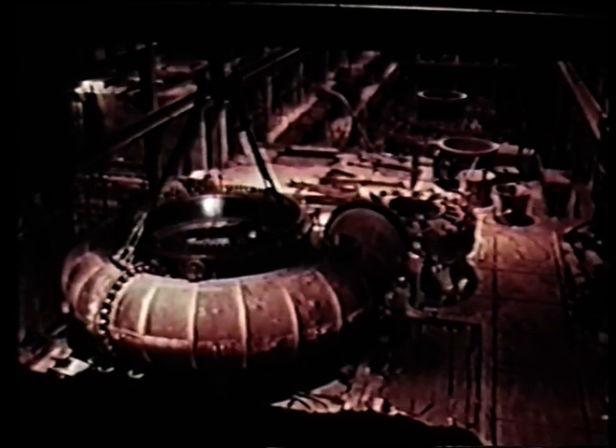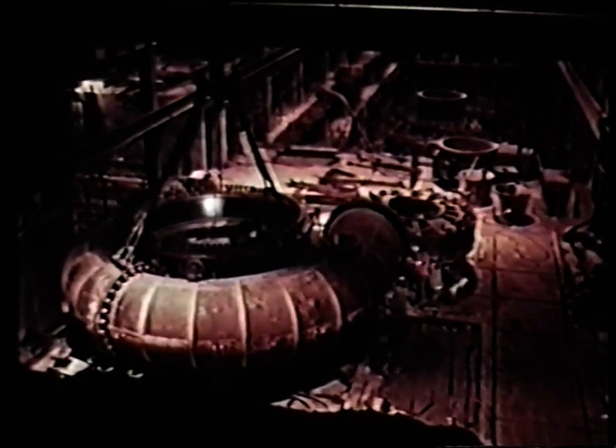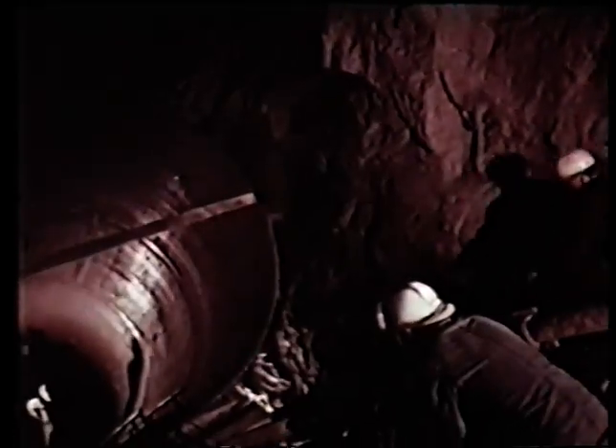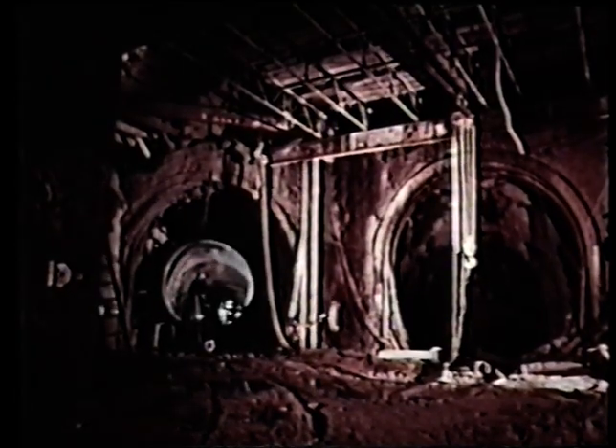The spiral casings were the first large-scale pieces reassembled in the machine hall. The halves are bolted together again, and the casings are pressure tested once more. The support barrels for the generators are added. The low setting of the machines and a surge chamber high enough to drain to the loch require long draft tubes rising 130 feet from the lowest levels. These are lined with steel sections 10 feet in diameter, welded together inside rock tunnels.